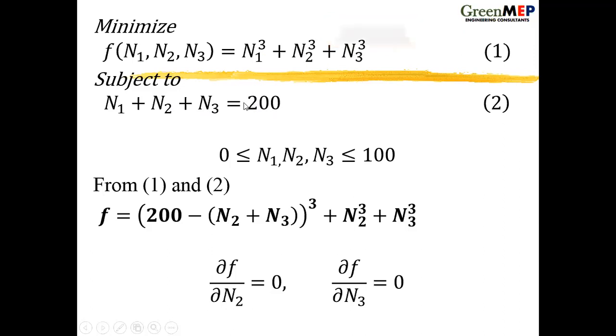We know that the total power, there are 3 of them. First one, speed n1 to the power 3, second one speed n2 to the power 3, third one speed n3 to the power 3. They can be constants coming up, but now the power is basically the first one speed to the power 3, the second one to the power 3, third one power 3. And then at the rated load, the speed should be 200, right? This means 2 rated, 200%, or you can say 2. 2 means you need 2 of them at the rated speed. That means speed 1, 2, 3, the sum should be 200. To meet the cooling load, or to do the cooling job, you have to satisfy this constraint.